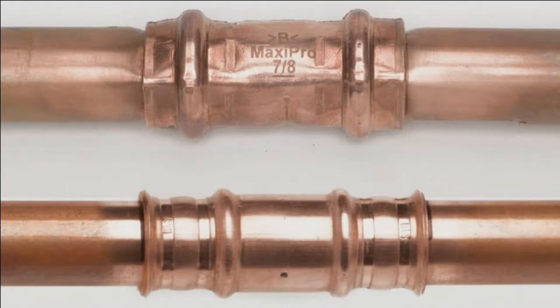Well, it doesn't look natural. Even my buddy Joe was in the chat and said he's surprised a square shape on either side of the O-ring still allows for a proper seal, but he's guessing it's just dragging that copper in enough to get it seated. But it doesn't look natural, it looks rough. I see it from a standpoint of refrigerant flow, not even the pressure it seals, but just the flow, it seems like it'd be interrupted so badly with that.